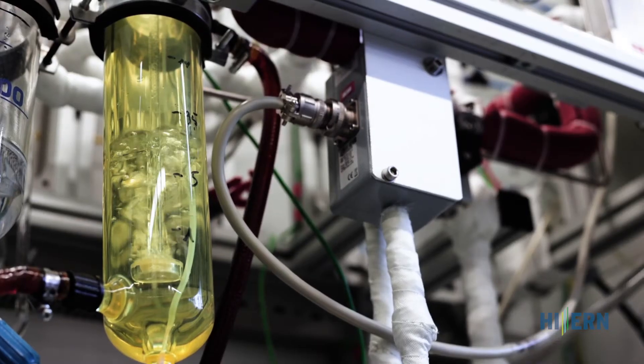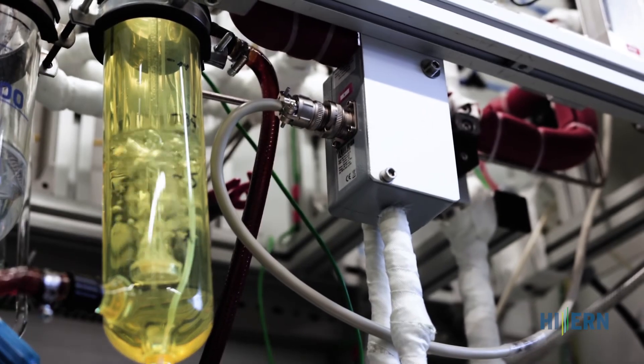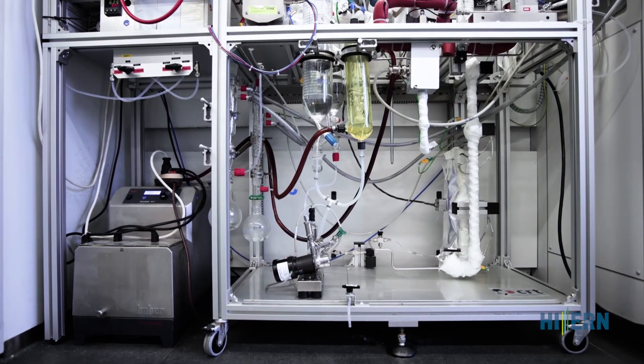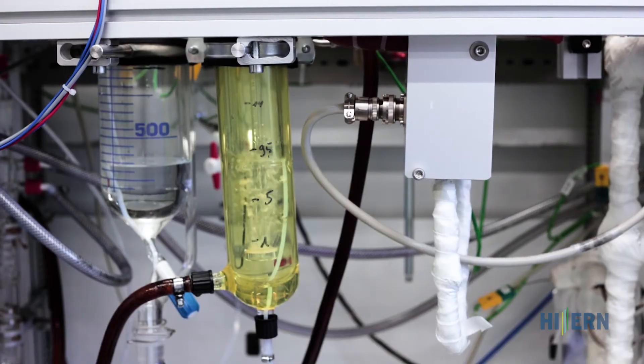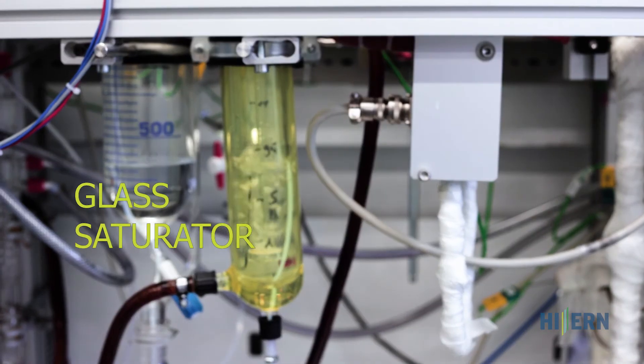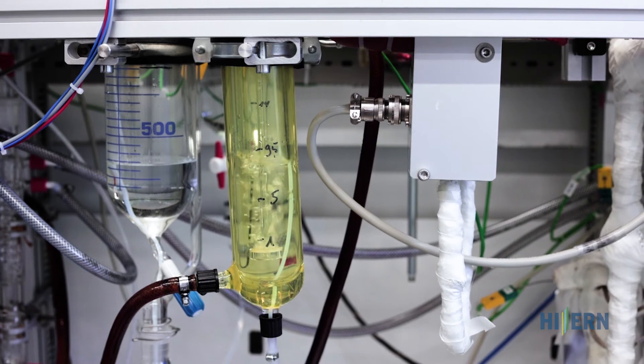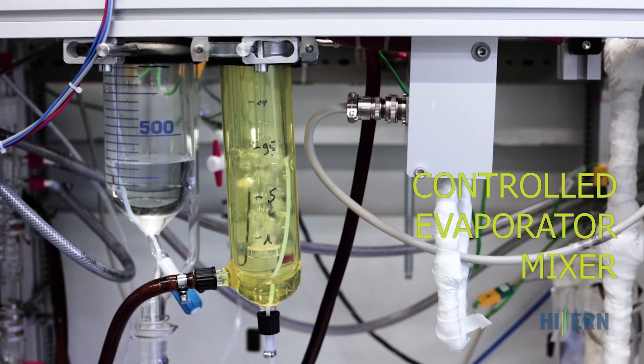The water balance is crucial for good proton conductivity and thus high power densities. Humidification of the cathode air takes place via a glass saturator. Humidification of the anode side takes place via a controlled evaporator mixer.